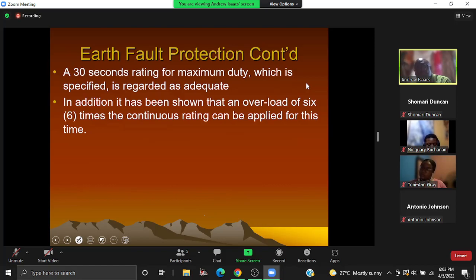So it means, therefore, that, given what we would expect as far as the operation of our relay is concerned, we know that in the scheme of things, we would never have a fault on a generator for 30 seconds. Are you with me? So although we specify this, these are just the absolute worst case scenarios. Even if your primary protection fails under these circumstances, there will be other parts of the protection system which would have operated outside of that 30 seconds. Because we know that within power system protection, we are dealing with milliseconds in terms of operation. So 30 seconds is our lifetime.